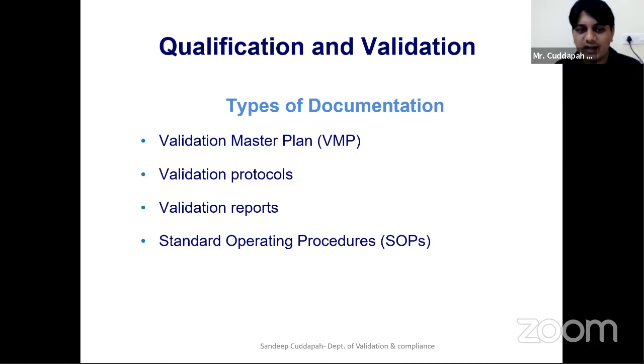Once you have included all the equipment in the master plan, for each equipment you will identify whether it is directly impacting the system, indirectly impacting the system, or not impacting the system. Based on the impact, you will identify in the validation master plan at what frequency you have decided to verify certain performance parameters that you will define under the validation master plan. For that verification purpose, you will prepare validation protocols and reports specific to each equipment.